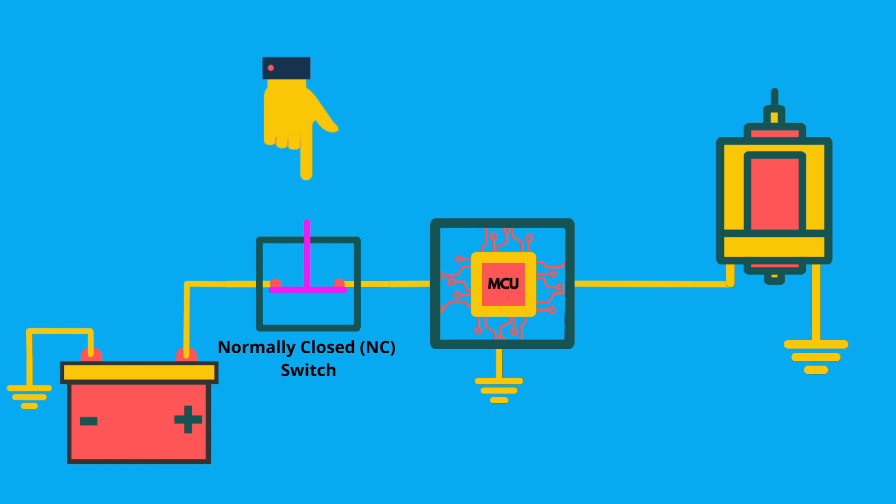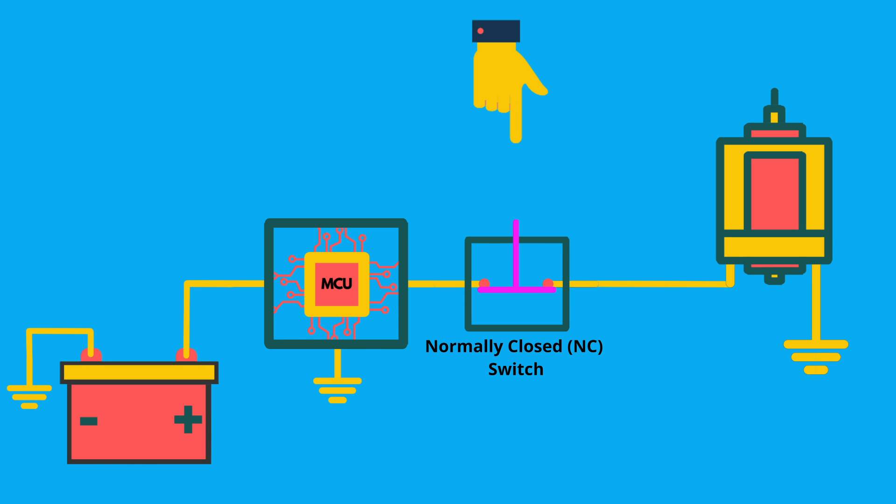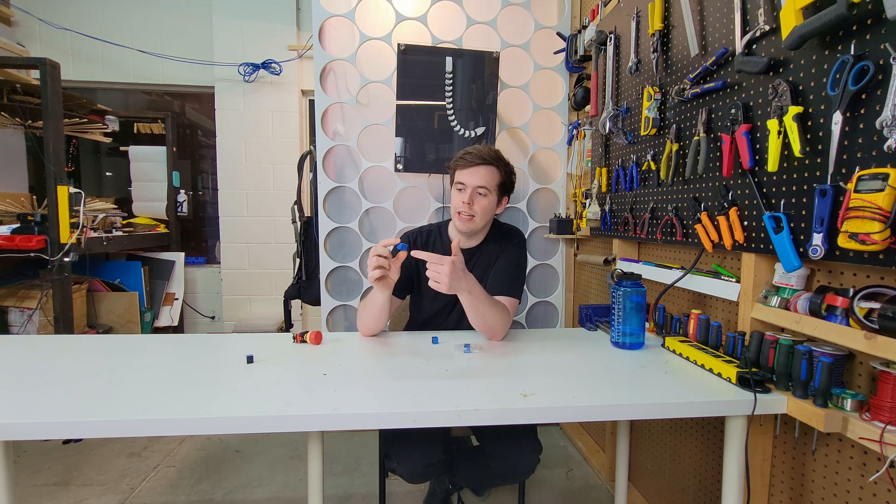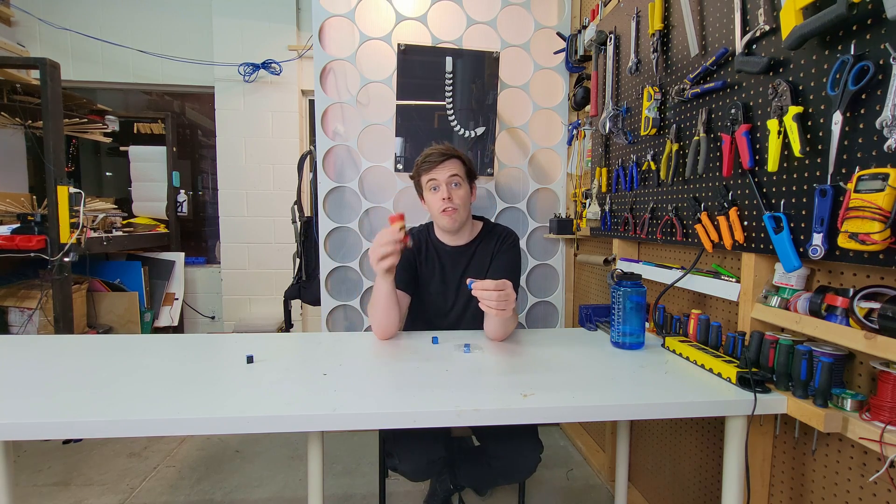Admittedly, we could resolve the second issue by moving the switch between the controller and the motors. That way, the controller can still be powered even when the switch is open. But the first and third safety conditions are still being violated. To resolve this, we're going to use relays that are triggered by the emergency stop button.